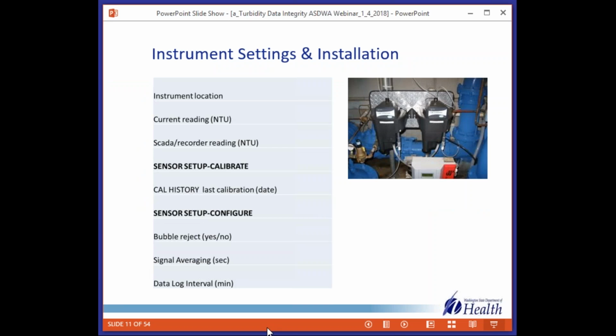So here's some of our data sheets. We look at the instrument location, and we would go to each instrument, look at the current reading, and then we would compare, at that exact same moment in time, what the SCADA or recorder was reading. So in some small plants, you can do that by just shuffling your feet maybe a little bit. In large plants, which are maybe minutes apart, we would use cell phones or radios to actually capture at the same moment in time what they were reading. All of the 25 systems used HACH products in this study, so we structured our forms to follow the controller logic path, and you can see some of the things that we looked for.